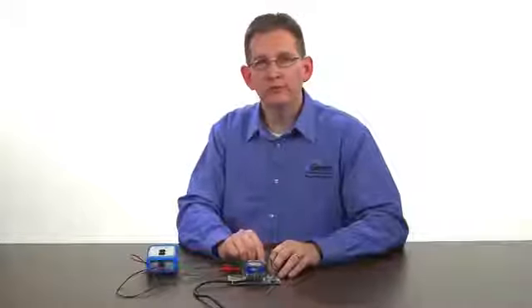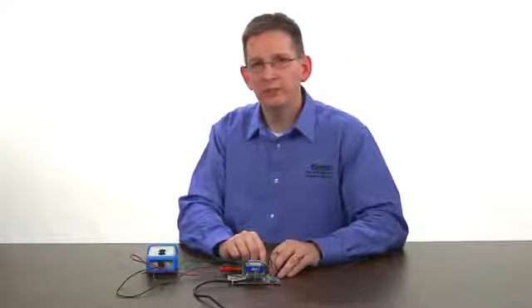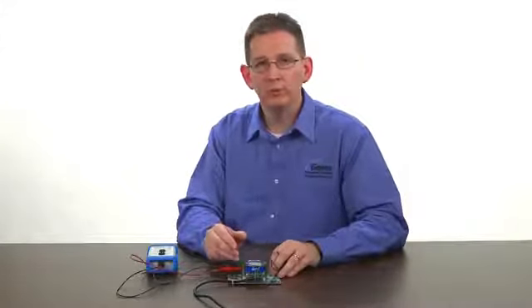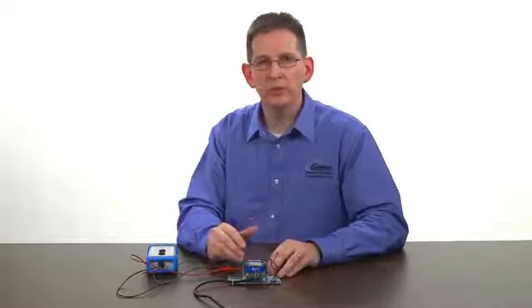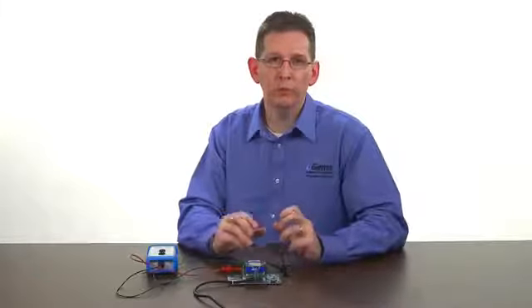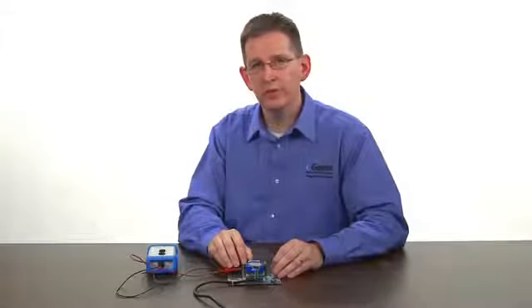Once you've checked your relay for proper functionality a few other things to consider. The cleanliness of your probes. Is there any buildup of material on those causing a case called bridging material between two probes or to the reference point. Also verify that you've wired your probes correctly and then you have nice tight seals and continuity in your wiring.